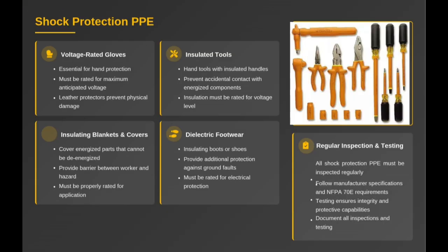When electrical hazards cannot be eliminated, PPE becomes the last line of defense. Shock protection PPE includes voltage-rated gloves, dielectric footwear, insulating blankets, covers, and insulated tools. Every item must be properly rated, regularly inspected, and tested according to NFPA 70E. Remember, PPE only works when it's in good condition and used correctly.